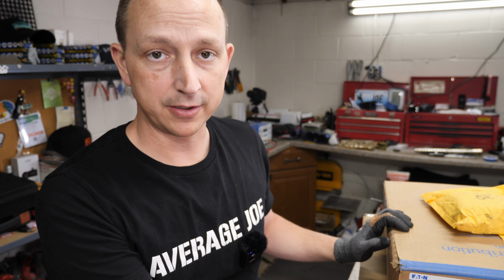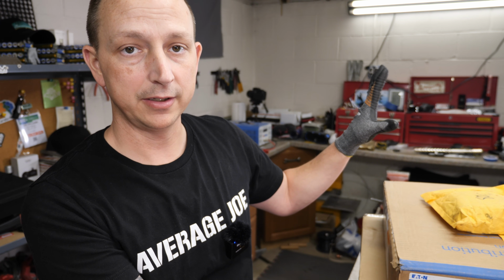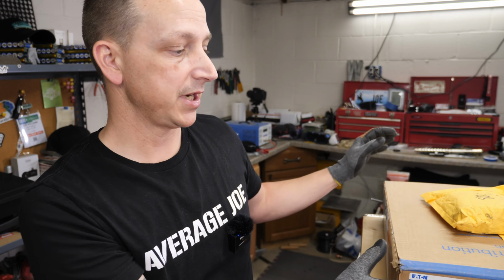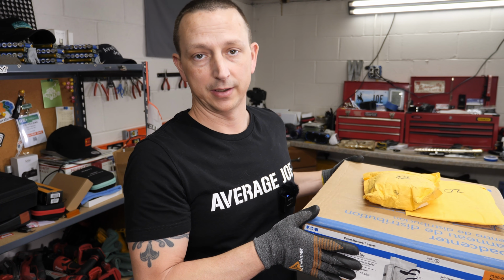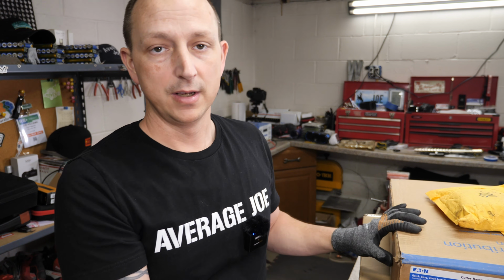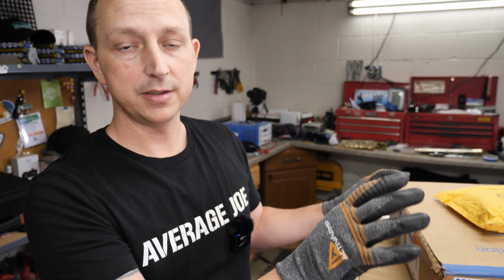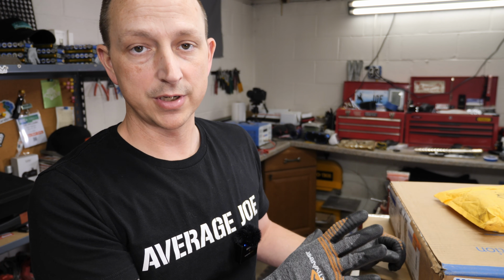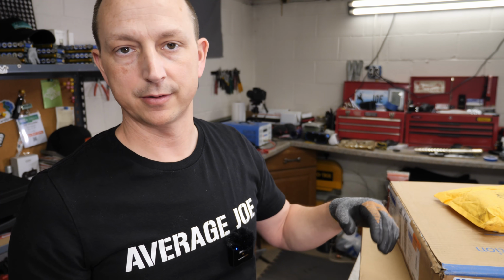Now how this works is you still have your main panel right here. You install the home panel in between a sub panel, which you can also buy as well—this one did come with that. You install this in between a main panel and a sub panel, so whenever the grid goes out for an outage or whatever reason, this automatically switches over and continues powering your sub panel. Once the storm or emergency passes and the grid comes back, this automatically switches you back on grid.